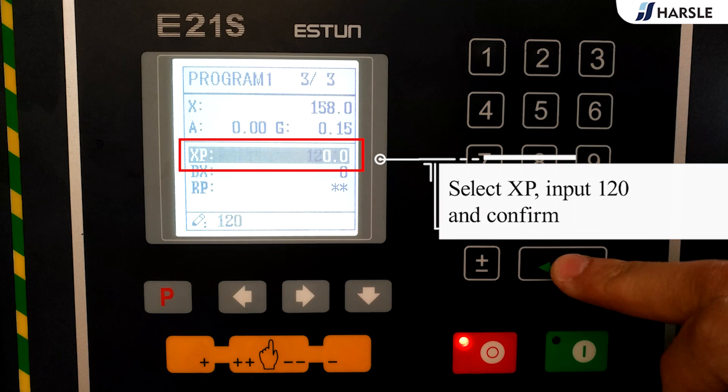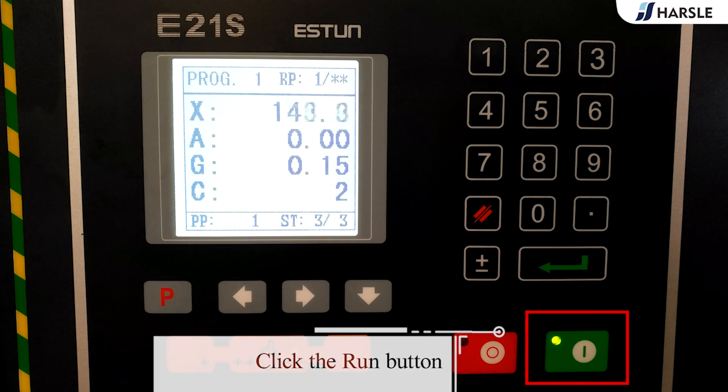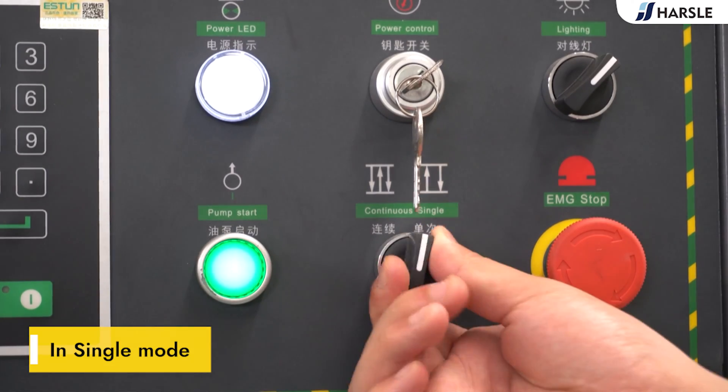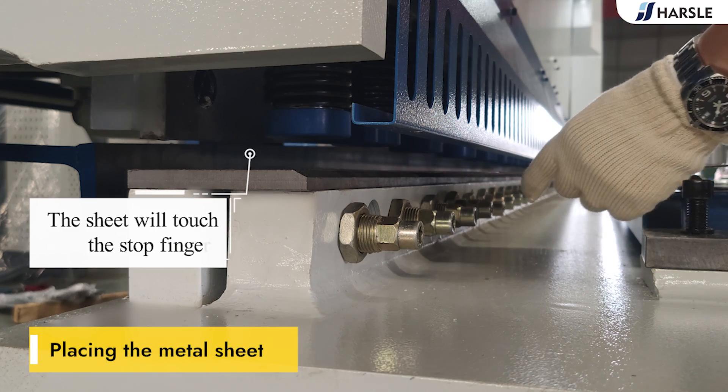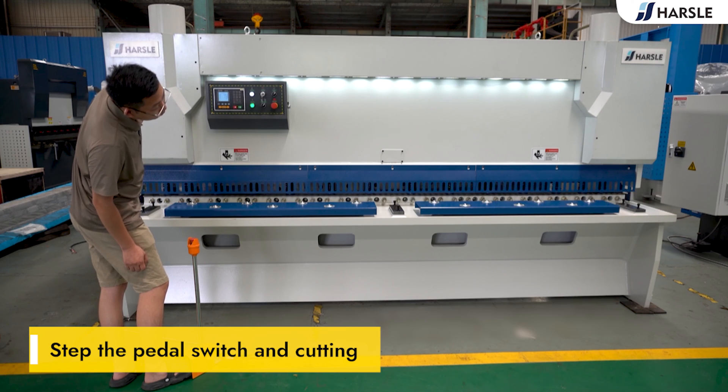Click to enter the third step setup page, select XP, input 120 and confirm. Click the run button. Part 4: cutting in single mode. Place the metal sheet — the sheet will touch the stop fingers. Step the pedal switch to perform cutting.